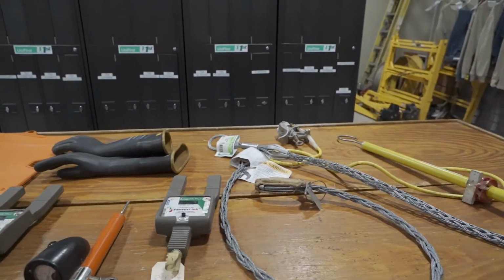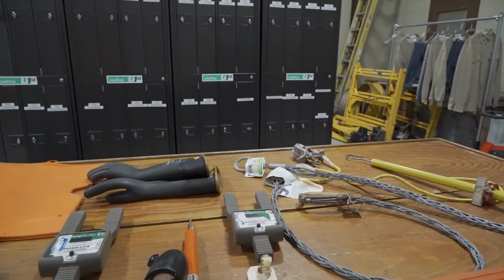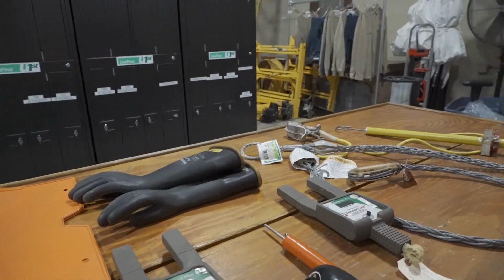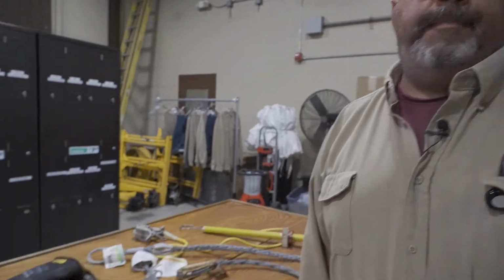And then everybody knows the rubber gloves. Those are tested every quarter, just to make sure there's no pinholes in them or anything that electricity can get through. They're tested to make sure there's no chemical burns, ozone, cuts or tears, that they're not damaged. So each lineman has 2 pairs, one pair being tested while they're using their other primary pair.